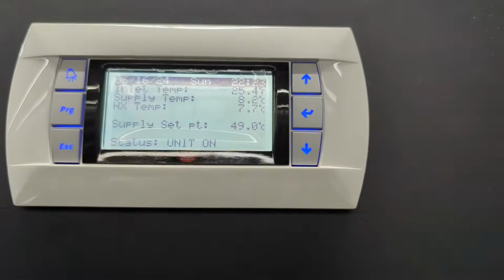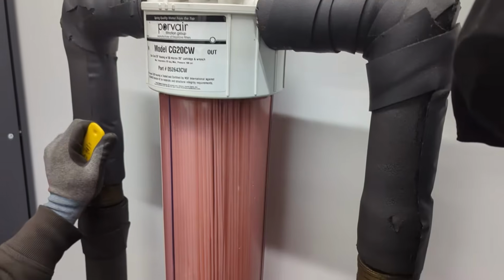So we went over there, we checked and cleaned all of the filters, all of the flow switches, like the paddle switches. And then finally we checked the tank, and the tank was just really low. The level of water and glycol was very low. So we topped her up, and that seemed to solve all those issues. The tank was actually just slightly low, not very low, just slightly.